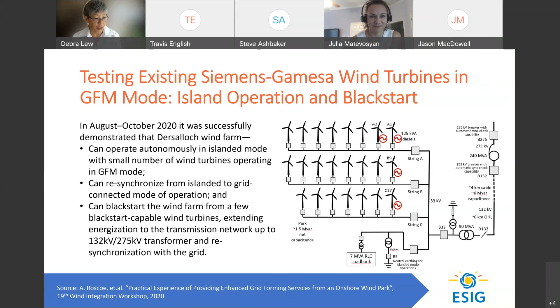They needed diesels to power up auxiliaries of the grid forming wind turbines so that they can start up, and then in grid forming mode you will power up the rest of the wind farm. So once they started these 4 wind turbines and powered up the entire island, they re-energized the 132 kV switchgear and the 132 to 275 kV transformer, and then resynchronized with the grid successfully. Next slide, please. Julia, you've got 13 minutes left. 13? Yes. Okay, should be good.